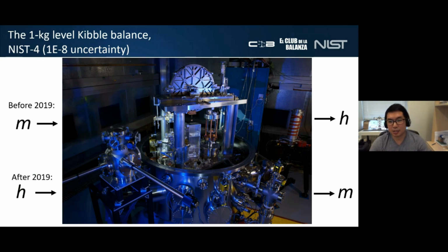So here's an image of our NIST-4 Kibble balance, and after 2019 it is capable of realizing kilogram level masses to 8 decimal places. That's basically being able to detect the mass of a fingerprint left behind on the shiny surface of the artifact being measured. So presently, this machine serves as the primary mass standard of the US. And what you see here is with the giant vacuum dome removed. And this instrument stands well over 2 meters tall.